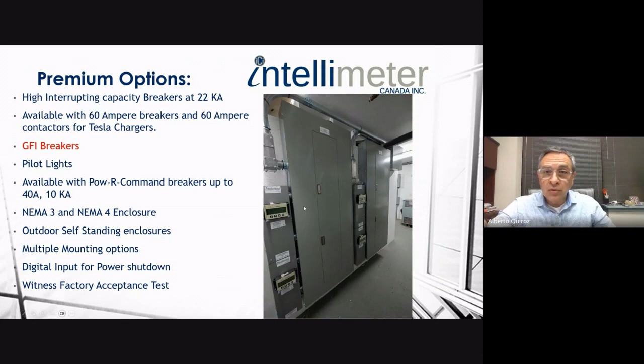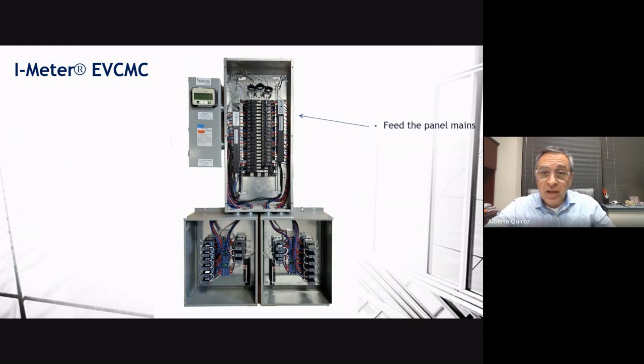That's something really unique to Intellimeter. Our system is very easy to install. Electricians love it because it's already done - they just have to feed the main lugs in the distribution panel through the current transformers provided for that. They connect the meter to the local area network just for reporting, though it's not necessary since access is totally local. Then they just connect the EV chargers from the secondary side of the contactors.